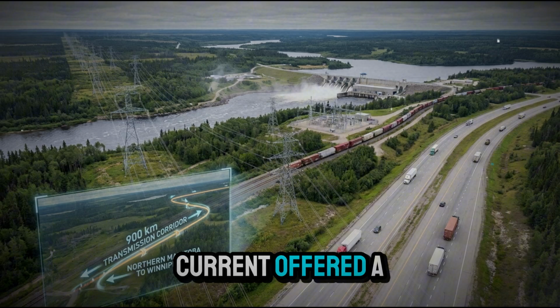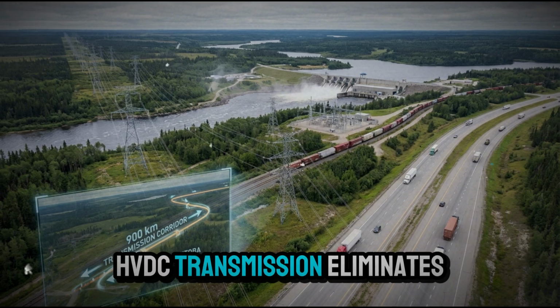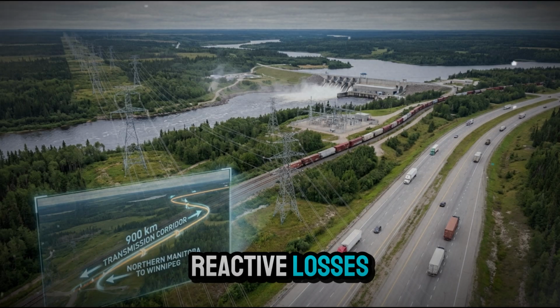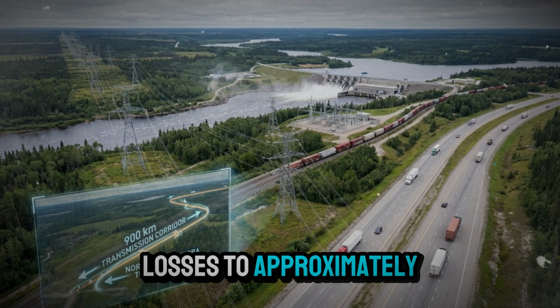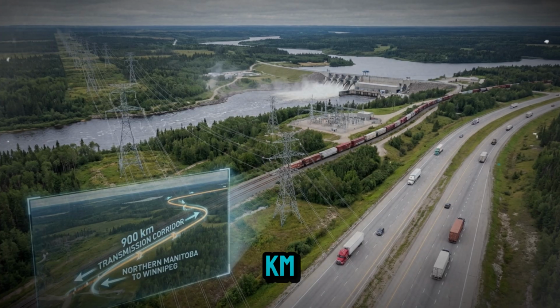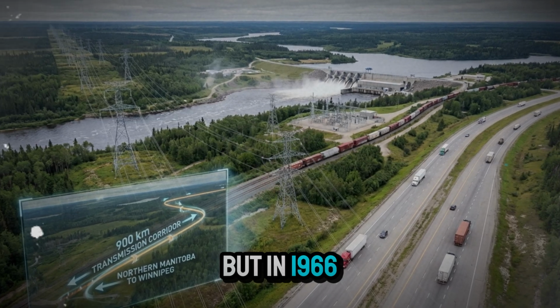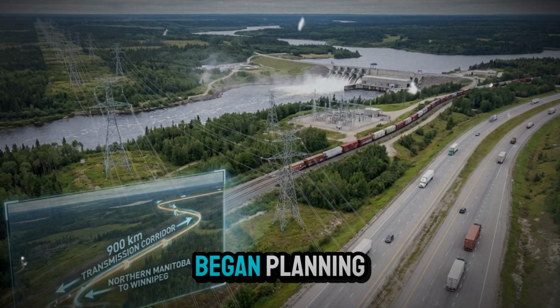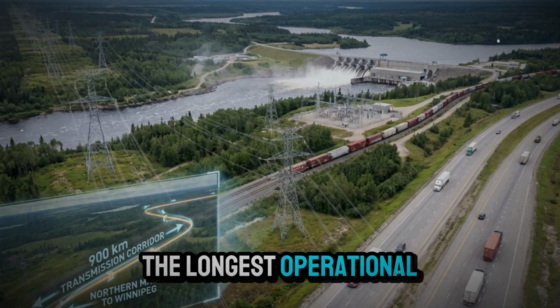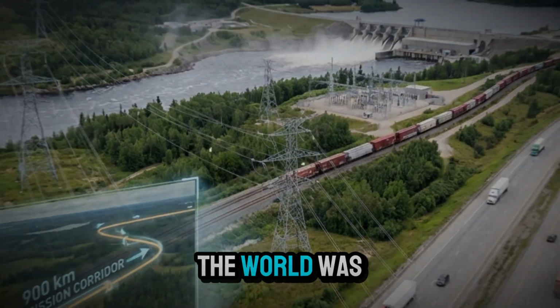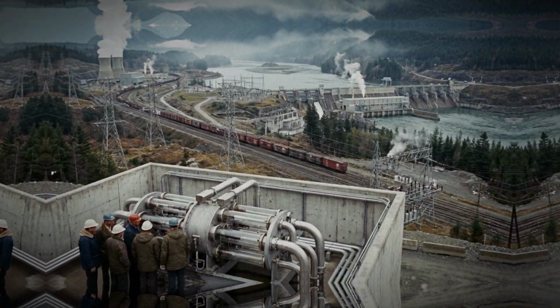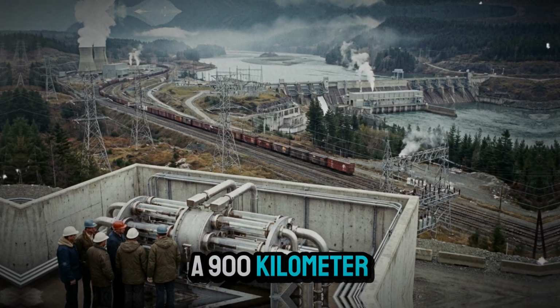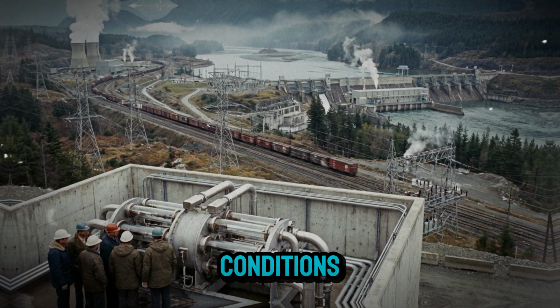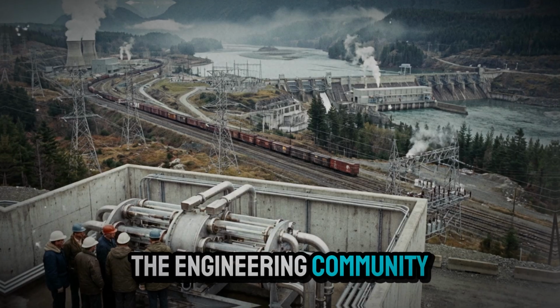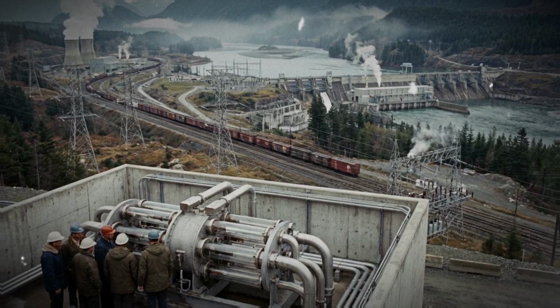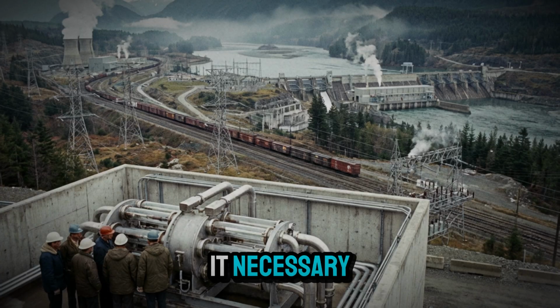High-voltage direct current offered a solution. HVDC transmission eliminates reactive losses and reduces resistance losses to approximately 3% per 1,000 kilometers. But in 1966, when Manitoba Hydro began planning, the longest operational HVDC line in the world was 850 kilometers. Nobody had built a 900-kilometer system through subarctic conditions. The engineering community called it ambitious. Manitoba Hydro called it necessary.